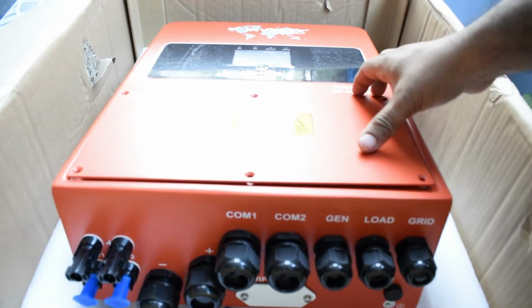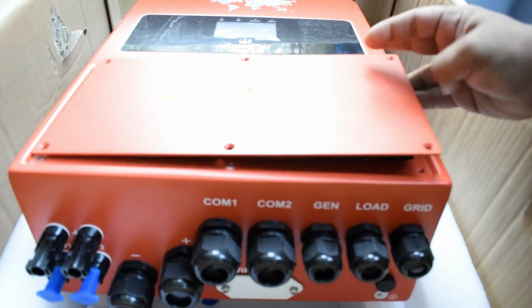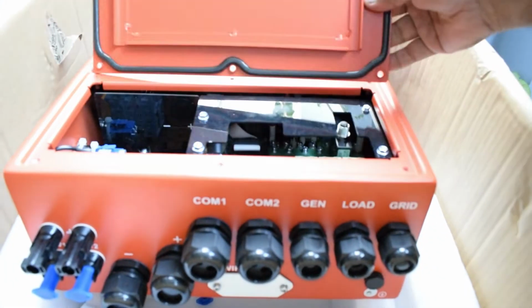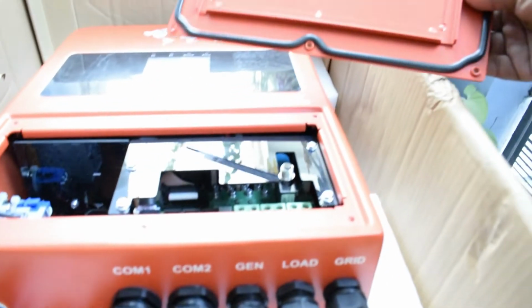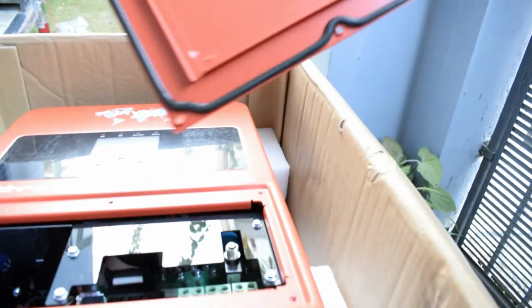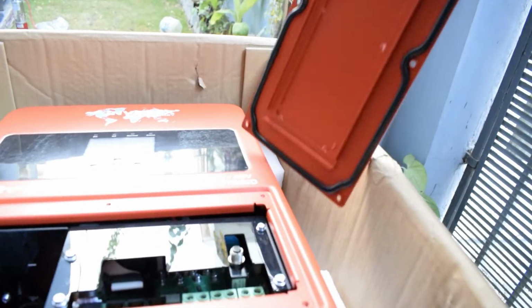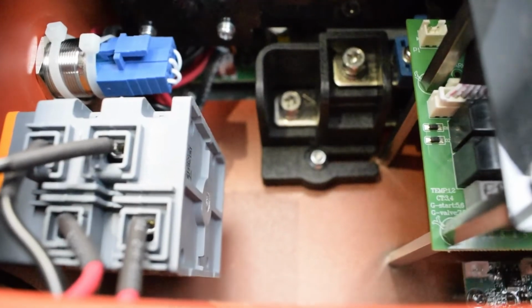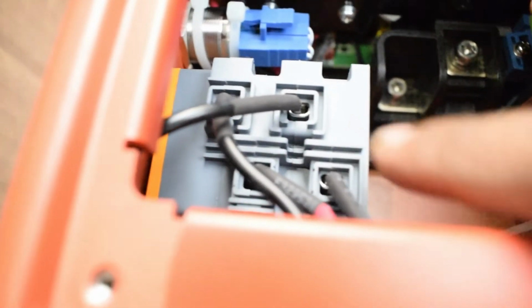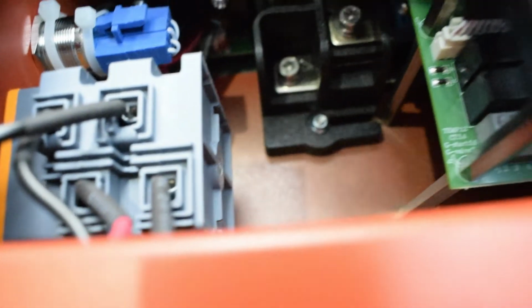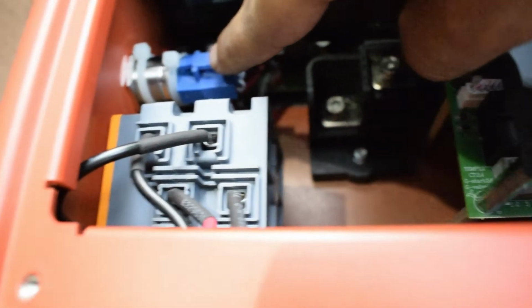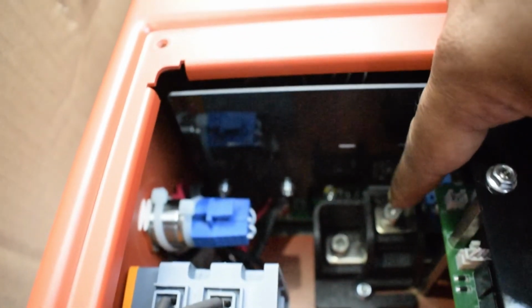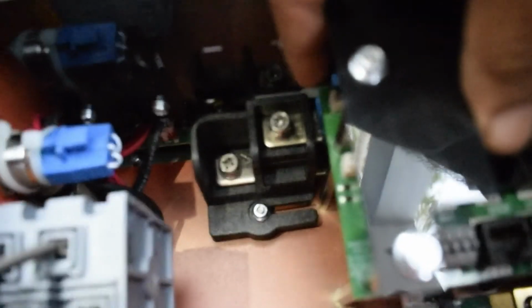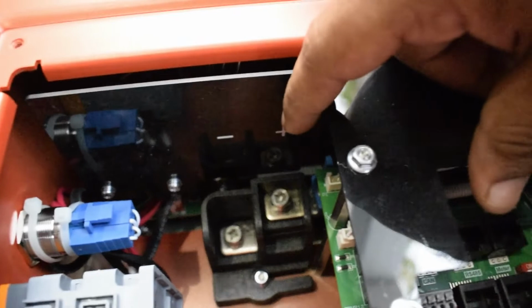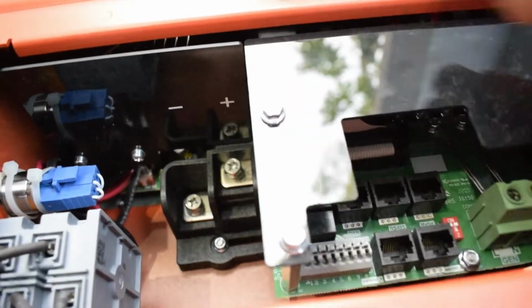Okay, so this is an IP65 inverter, IP rating of 6 and 5, completely dust proof and water splash proof. You can see the insulation of the cover box. Now, these are the solar panel switches for on and off, and this is the inverter button for on and off, and this is the batteries connection, minus and plus, the main connection, plus and minus for 48 volt batteries.